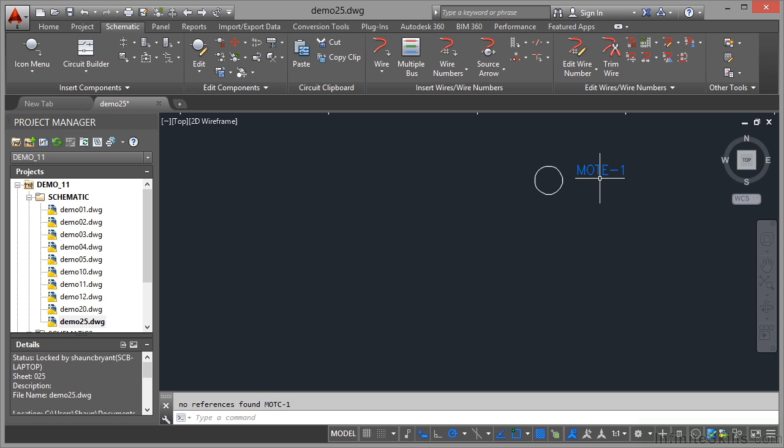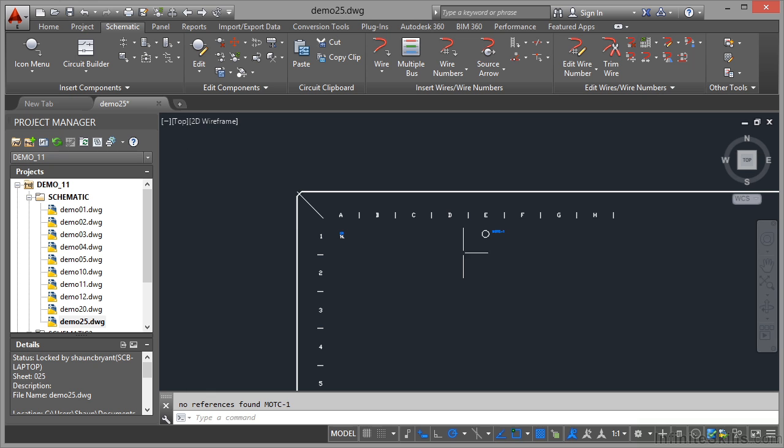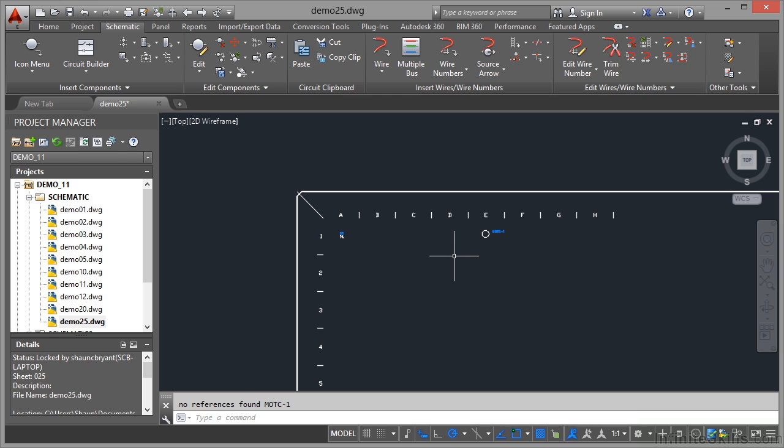If I OK to re-tag that and zoom in, it's now E1. That's why these grids are useful, especially when you're going symbol to symbol rather than have a logic ladder. You might be going point to point on a circuit starting at A1 and going across to E1. Any components going across from A1 to E1 will pick up on that grid. That's why these XY grids when you're referencing are very useful in your AutoCAD electrical drawings.